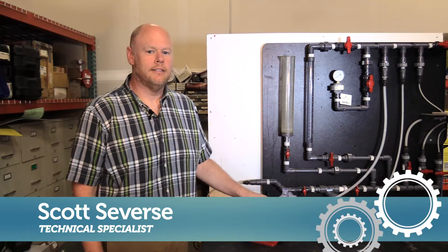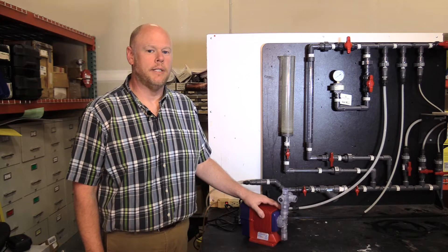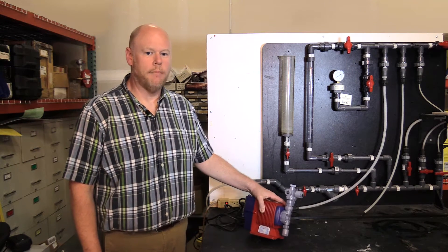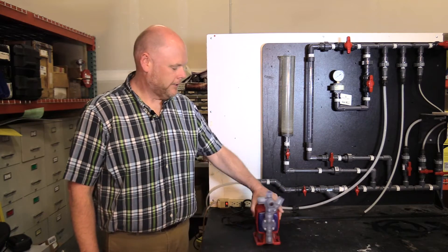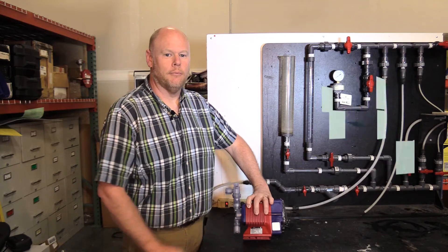Hi, my name is Scott. Today I'm going to show you how to rebuild your Iwaki Walchem metering pump. We have an EWN Y module pump. On the side of the pump is your model number and serial number. The model number is important to get you the proper rebuild kit.